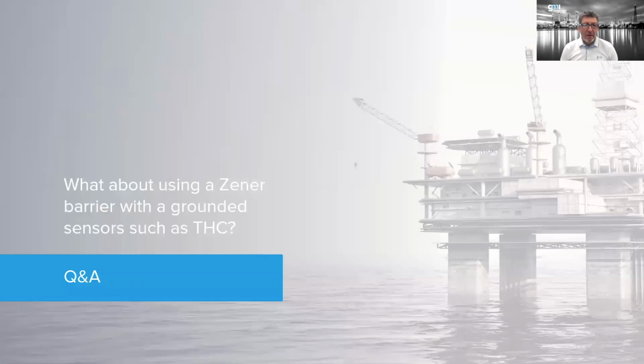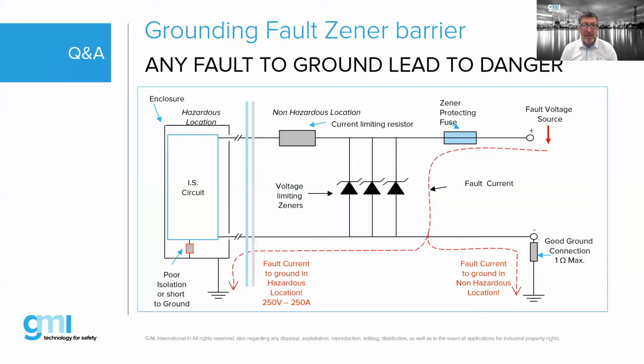Okay. Well, we already answered this question during the presentation. What about using a Zener barrier with a grounded sensor such as a thermocouple? We said you cannot, because if you have two ground connections, you have no means to control the fault current going to the hazardous location, right, Bob? Correct. And we don't know what the impedance is. You have one over here. How many ohms you have there? Nobody knows. So the current will be diverted and will share among the two different impedances, if I understand this correctly. All right, let's go next.